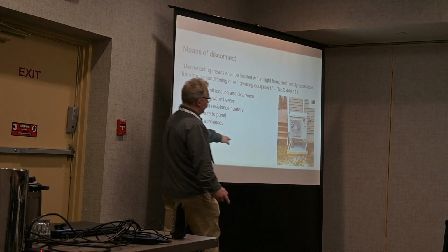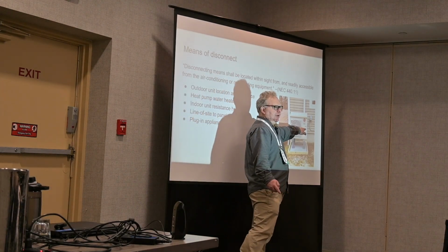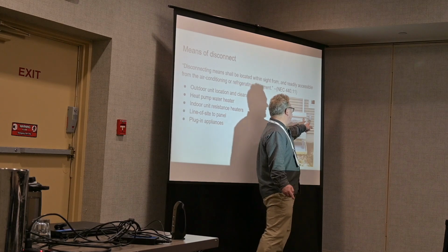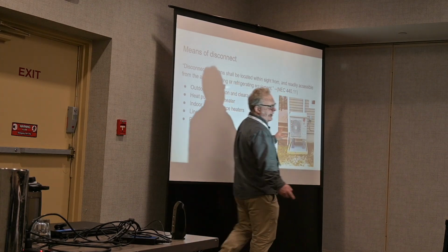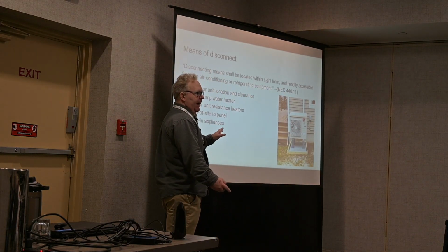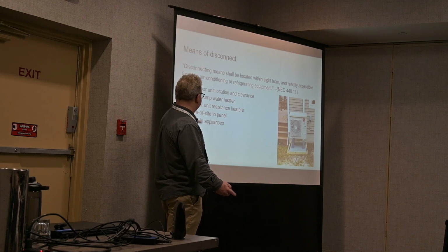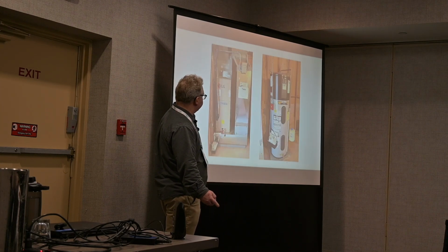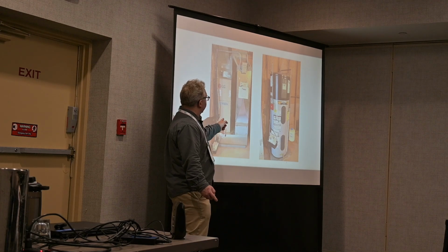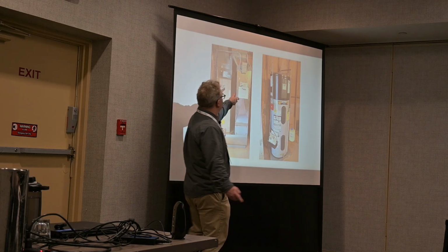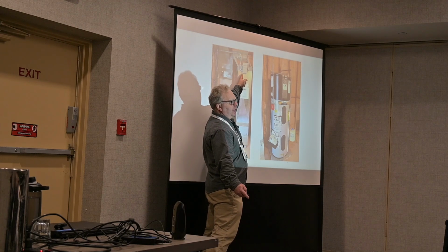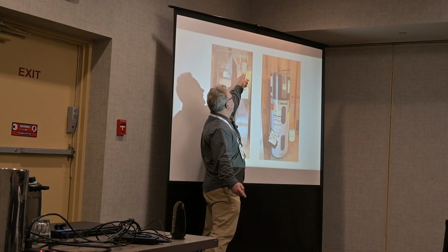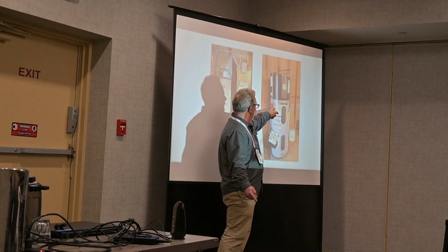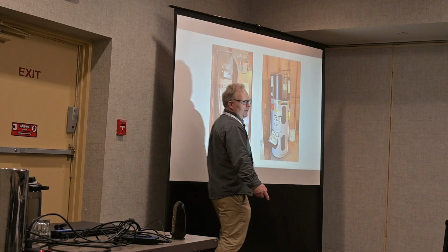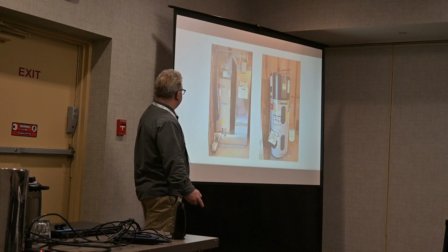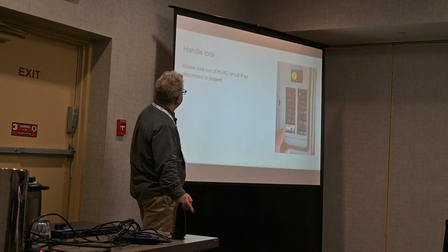We need to have a means of disconnect at every unit. This can either be a standard disconnect like the one shown here, or an outdoor sub-panel or panel, but it needs to be within line of sight. The heat kits on air handlers are powered separately, so we'll need a disconnect there. Same thing with heat pump water heaters. If they're not in direct line of sight of the electric panel, you will need a disconnect on those.